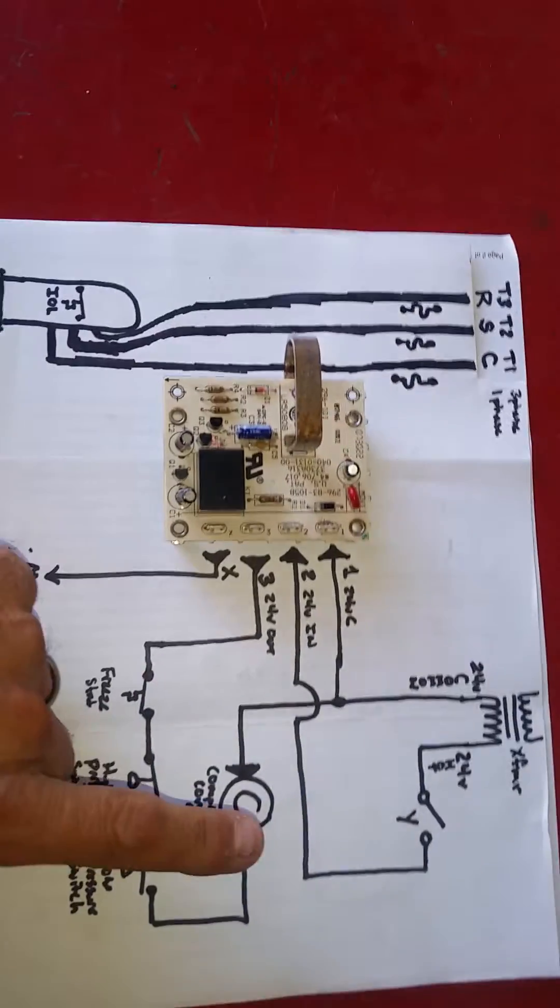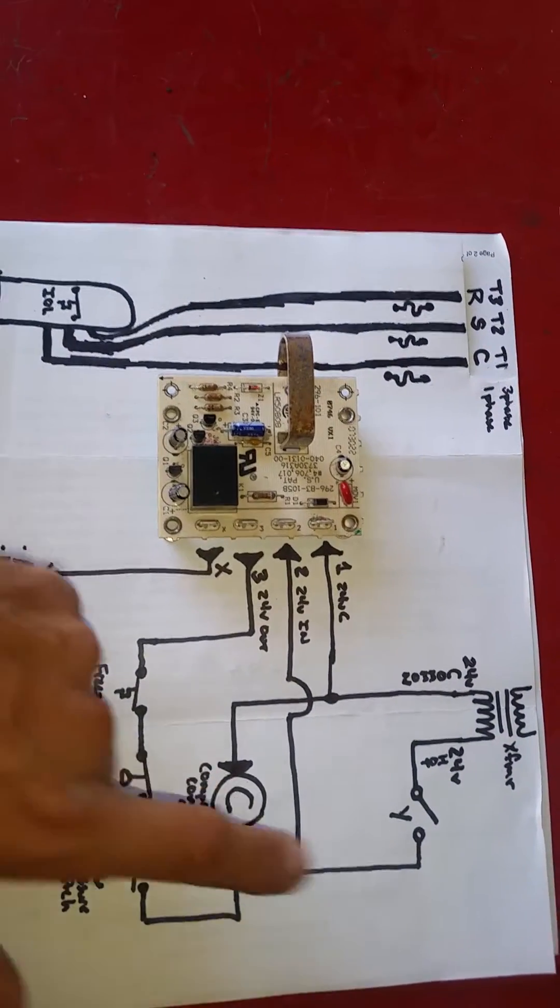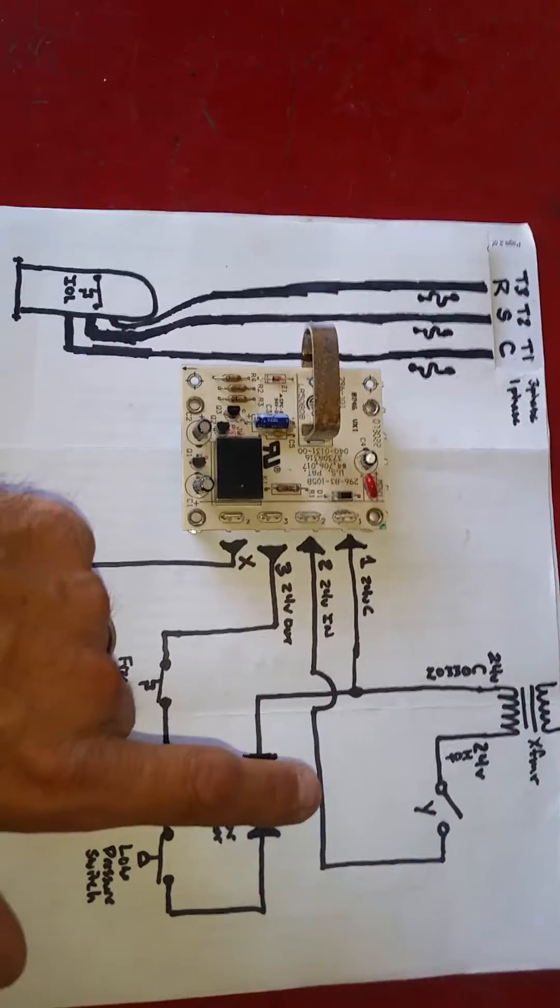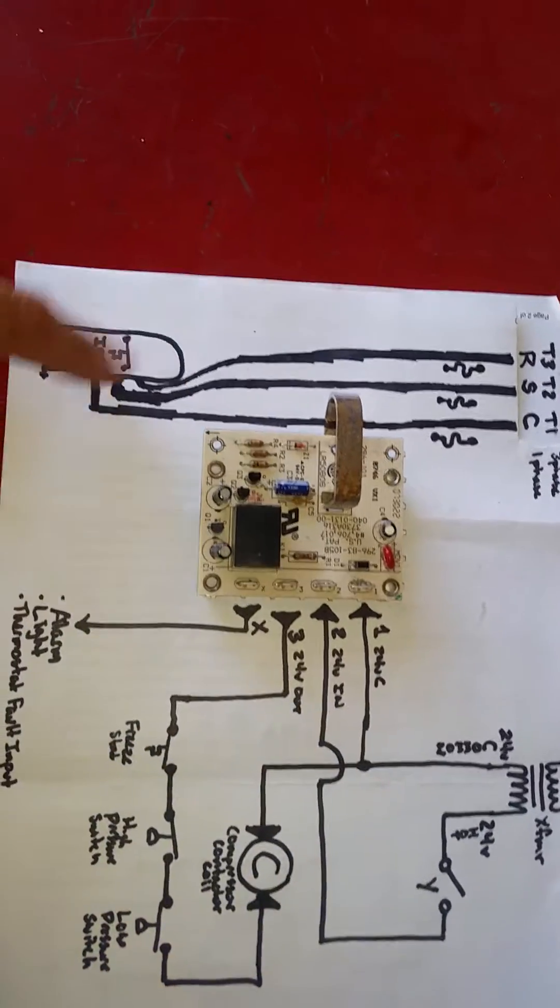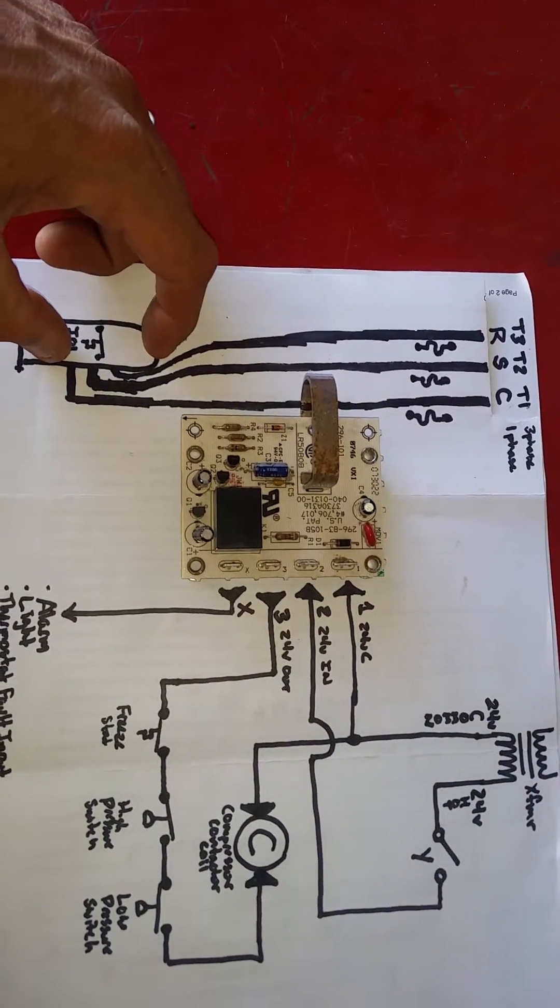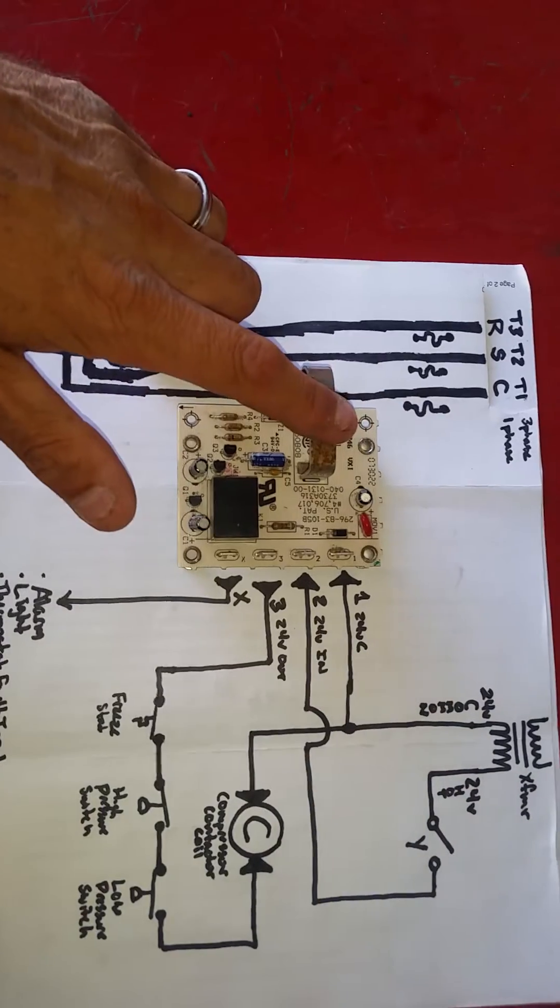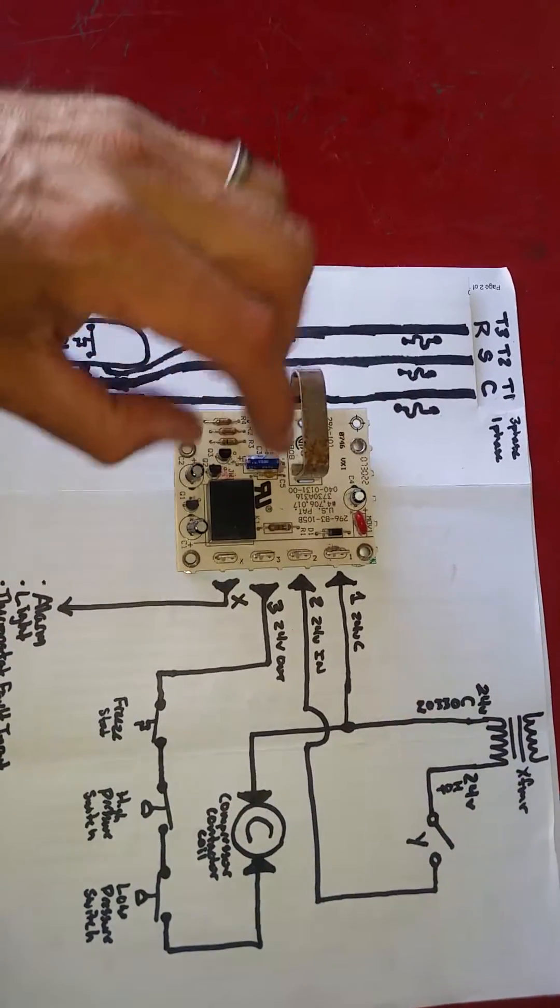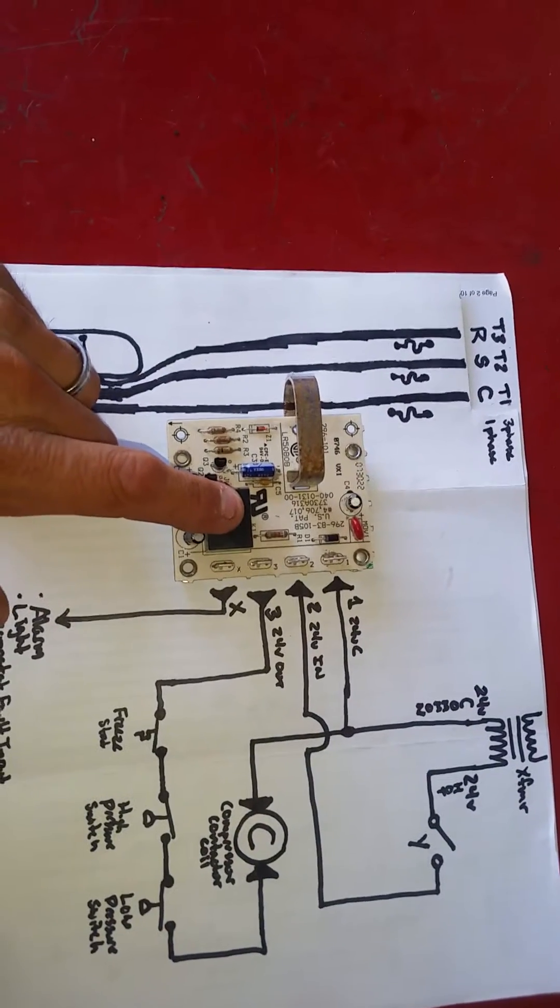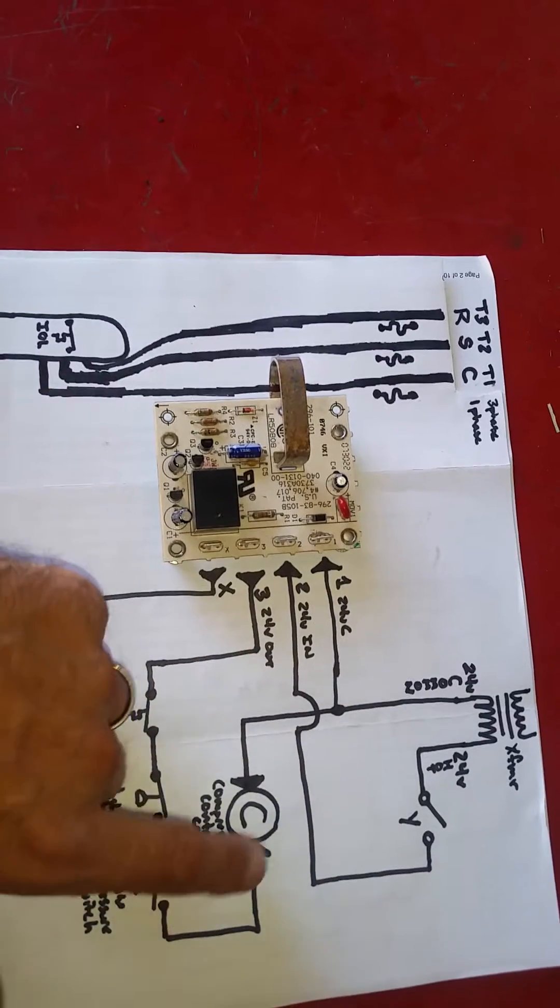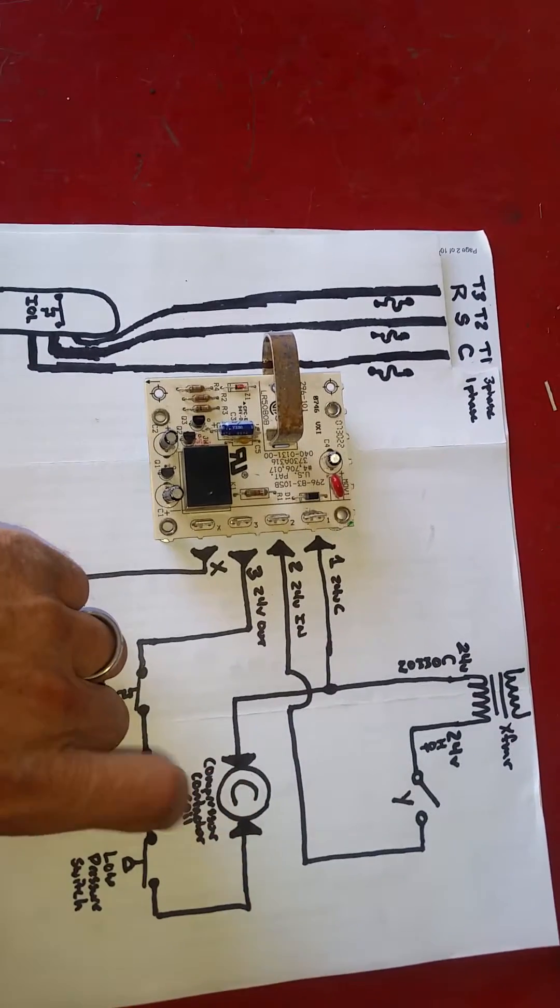Thus, as a compressor contactor closes, because we have 24 volts coming through the normally closed relay through three, as this closes, our compressor draws amperage, and of course this is going to draw more than 2.5 amps. This will sense more than 2.5 amps and keep this circuit de-energized and this relay closed. That way we will have continuous 24 volts feeding our compressor contactor.